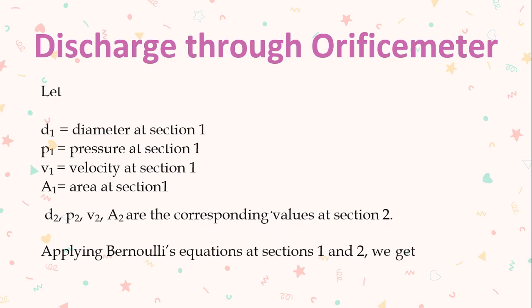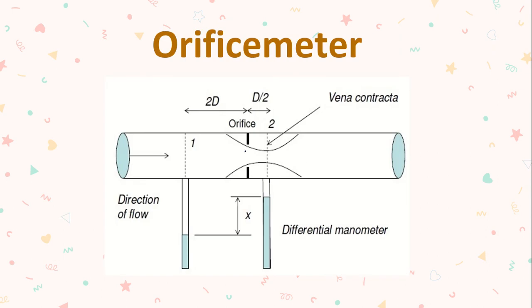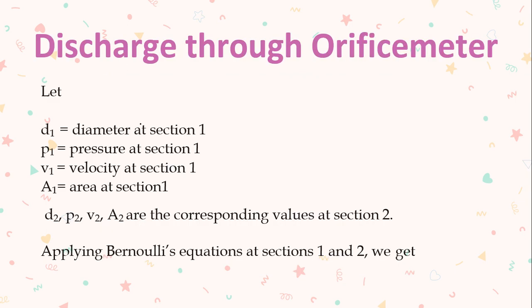Now let's derive the expression for discharge. We connect two sections: section one is just before the orifice where water enters the orifice plate, and section two is at the vena contracta. D1 is the diameter at section 1, which is the pipe diameter. V1 is the velocity at section 1, P1 is the pressure, and A1 is the cross-sectional area equal to π/4 × D1². Similarly, D2, P2, V2, and A2 are the corresponding values at section 2.